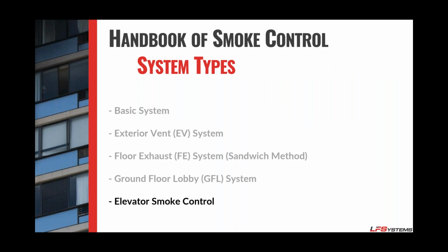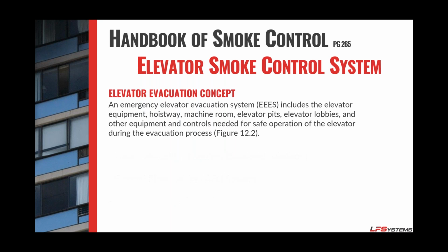So there's a fifth system. Like I mentioned, there were 4 systems listed in Chapter 11. Once you get into Chapter 12, it's called the Emergency Elevator Evacuation System. It includes the elevator evacuation concept. That's a lot of E's. I wouldn't recommend saying that too many times quickly. But the EEES includes everything involved with the elevator hoistway. So the elevator, the shaft, the machine room, the pit, the lobbies, everything else that's involved in the elevator is part of your elevator smoke control system.